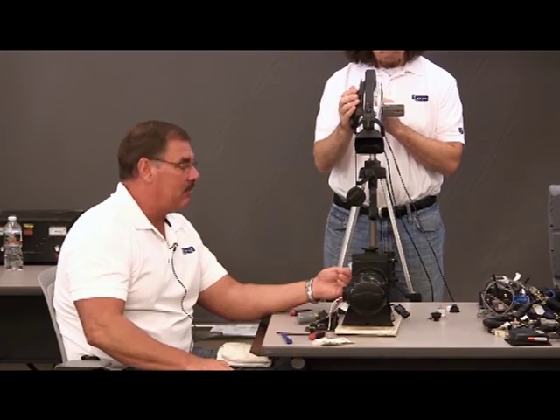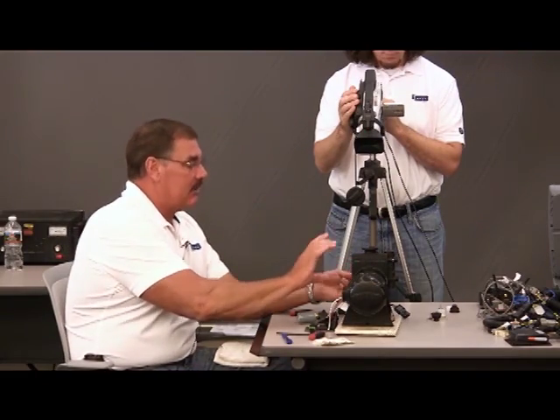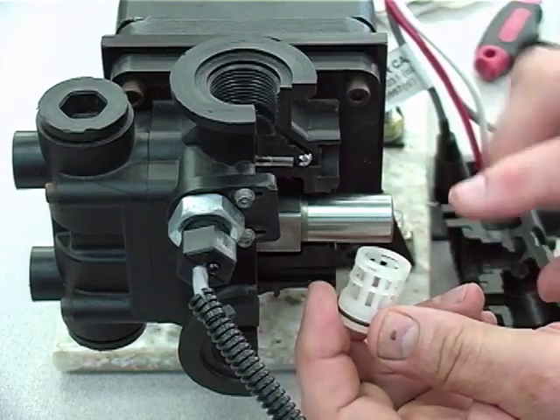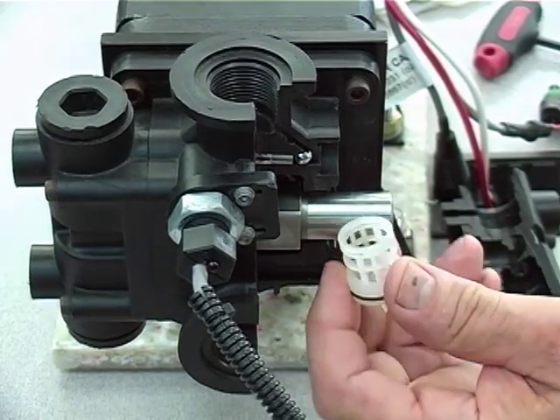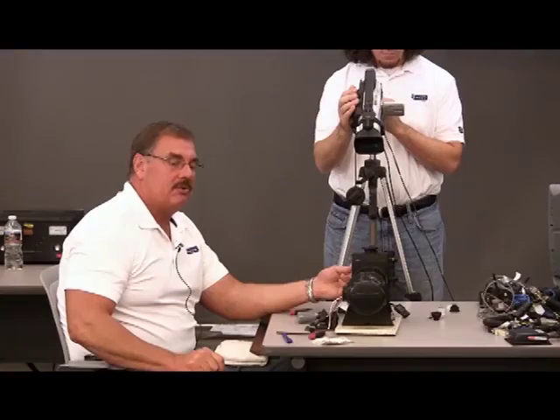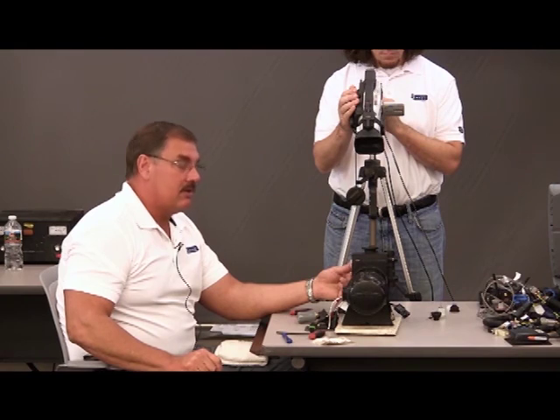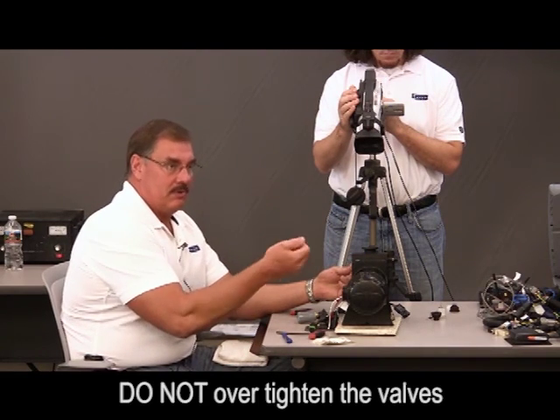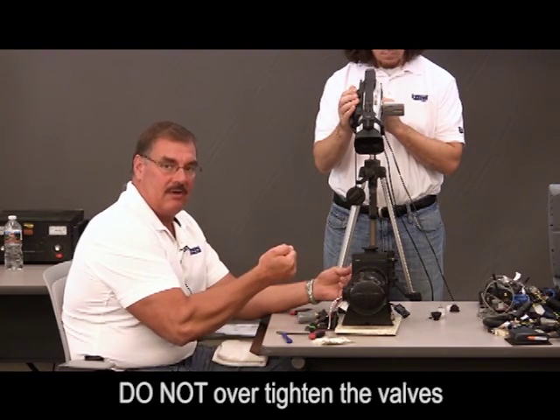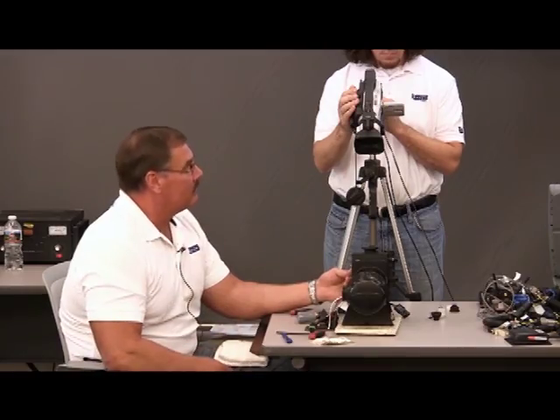It's kind of a pick your poison. Either replace one of these things or replace a whole pump head, which is quite a bit more expensive. Like I said, you can crush or turn these things crooked two ways. Either you deadhead the pump or you over torque it when you're trying to turn them in. You can turn them in too hard and you can crush those valves on there.